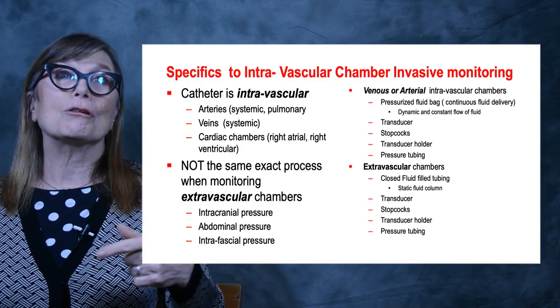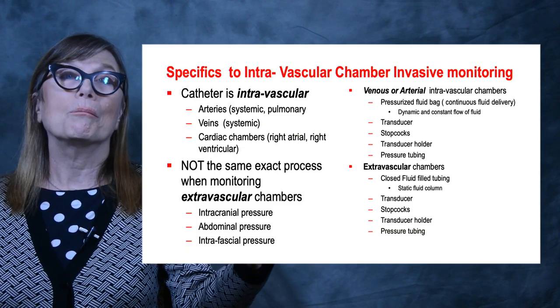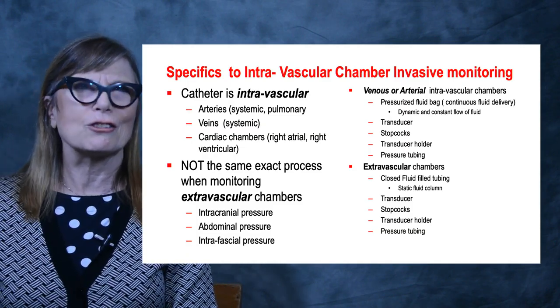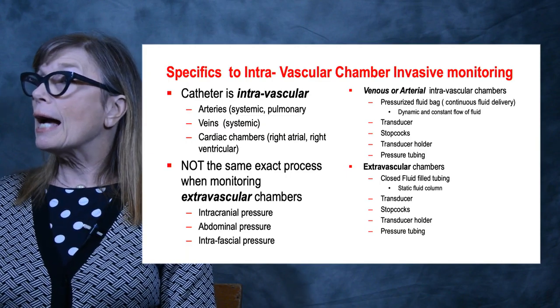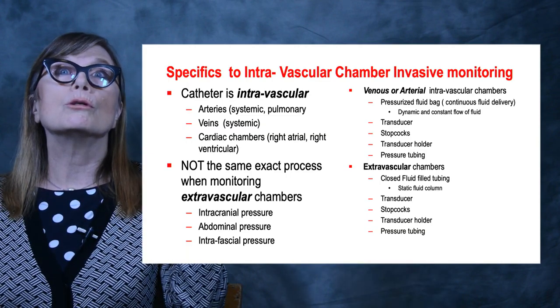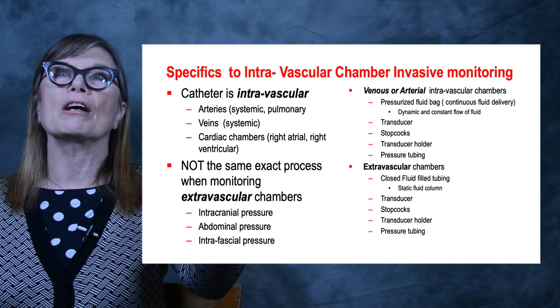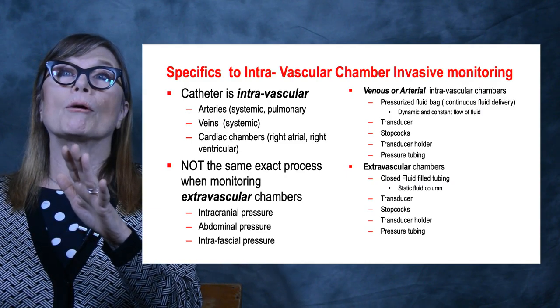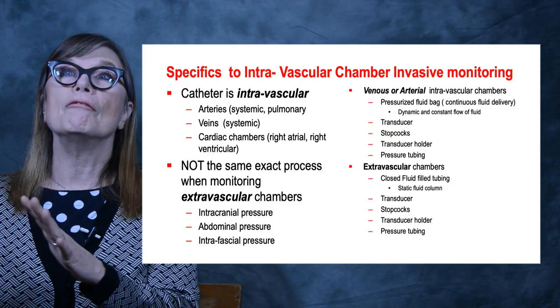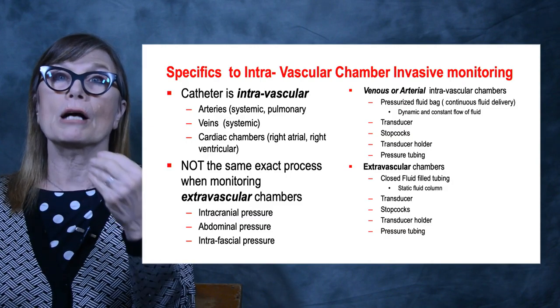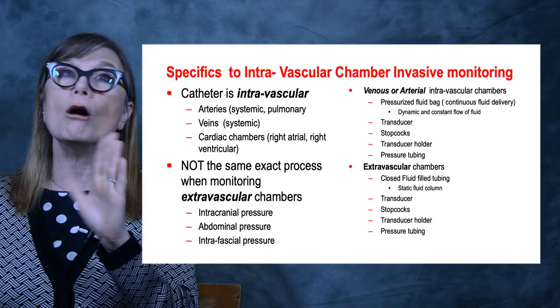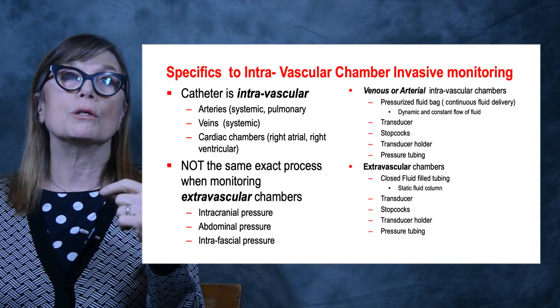The transducer is also connected to pressure tubing. We're going to take a look at that in just 1 second. With extravascular chambers, you do not have pressurized fluid bags. That's the one thing that's different. The extravascular chamber has a closed fluid-filled tubing system, the pressure tubing system. That's a closed fluid system, not a continuous fluid system.